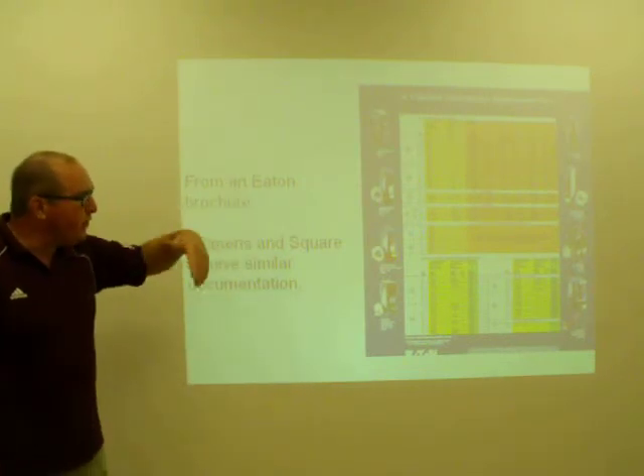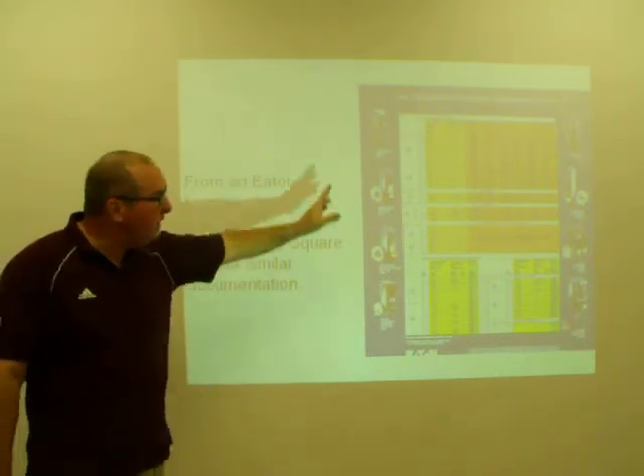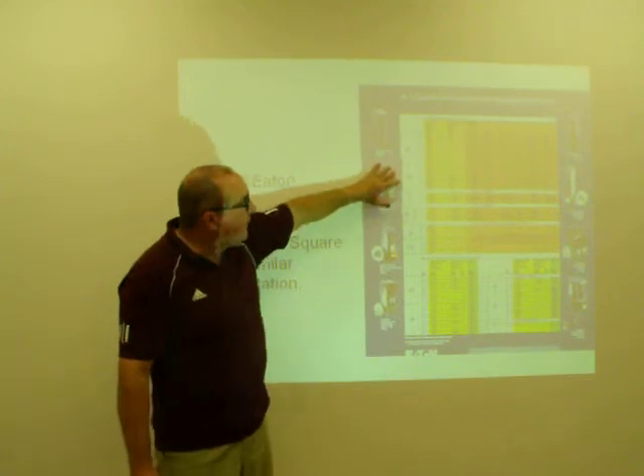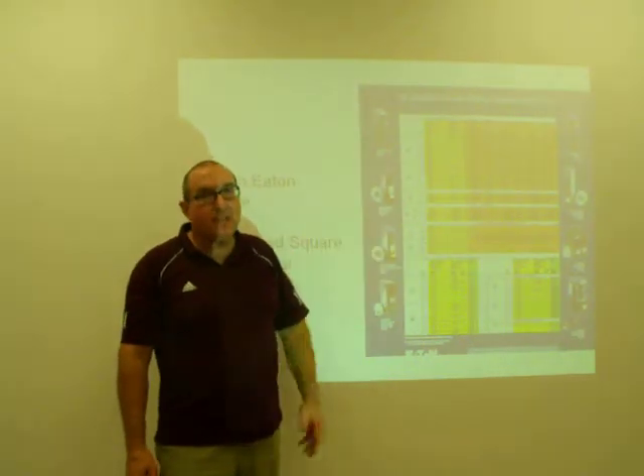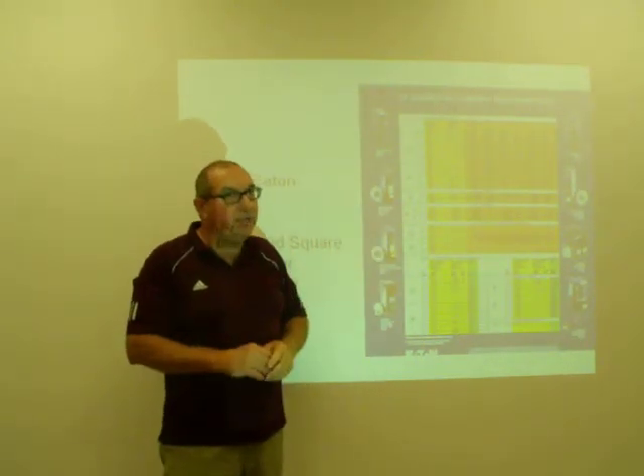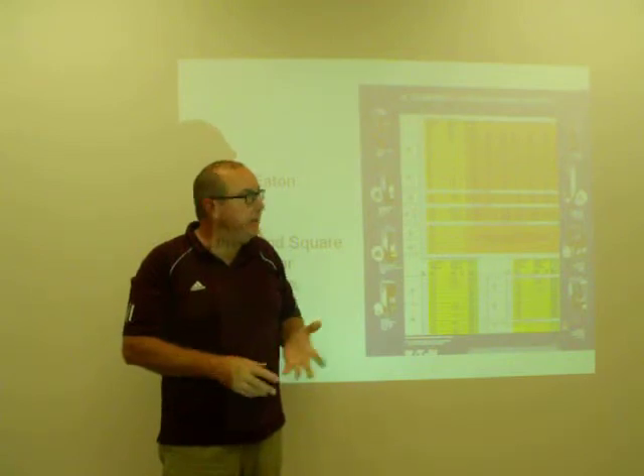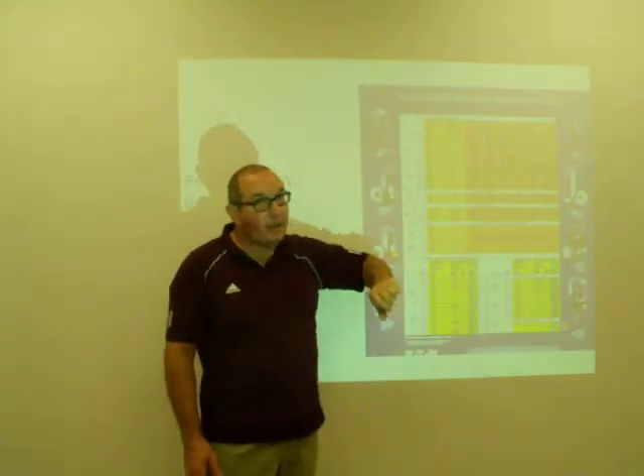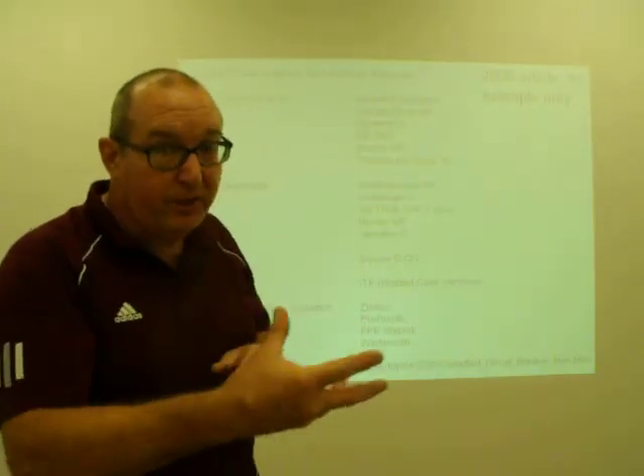And Eaton publishes a brochure, as do Siemens and some other companies, that will give you a listing of brands of their breakers that can be used in other brands of panel boards based on their UL listing. Again, they even make some that will fit Square D panel boards, although Square D will tell you that there's no other breaker than theirs that is authorized for use in their panel board.